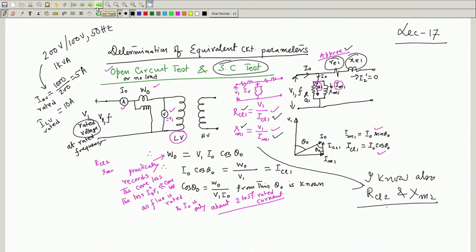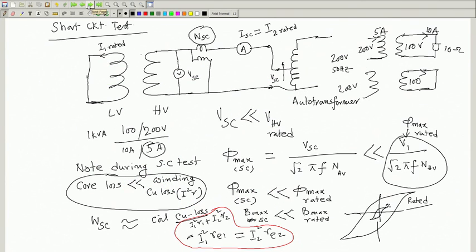I have not yet told you why the open circuit test should be done from the LV side — that I will discuss today. If you carry out the short circuit test, it is better to carry it out from the HV side. If it is carried out from the HV side, then the parameters you will get are RE2 and XE2. The calculations are pretty simple.